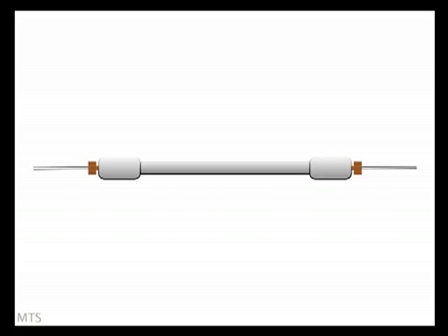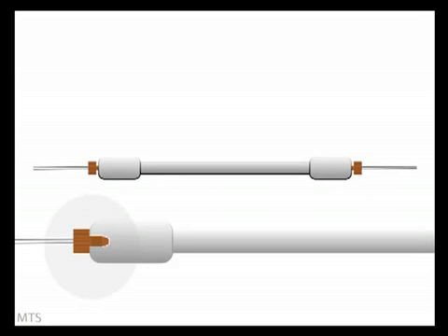As a consequence, the tubing needs to be connected in such a way so as to withstand the high pressure. This is achieved by the use of compression fittings. These fittings screw securely into the ends of the column to create a leak-free connection.